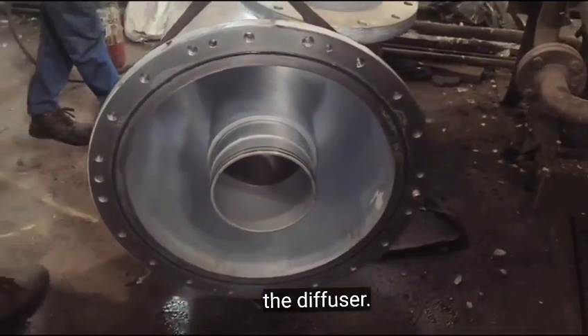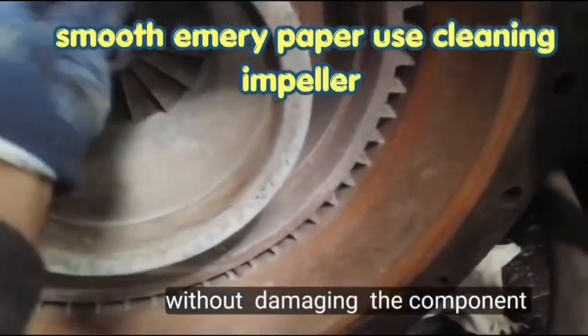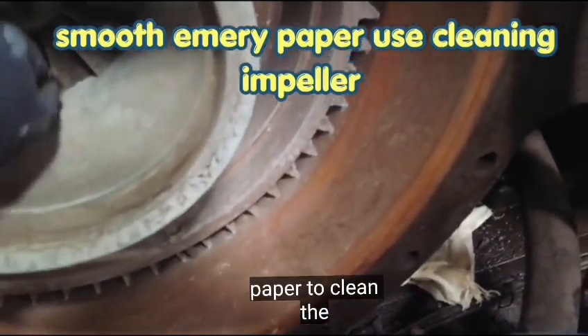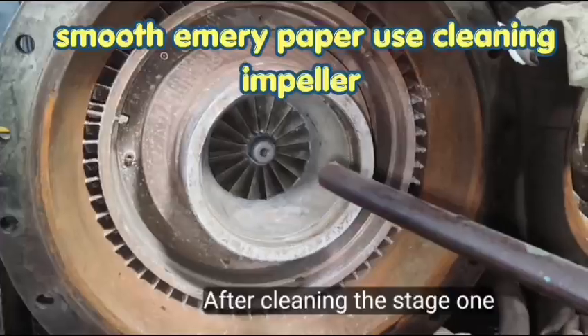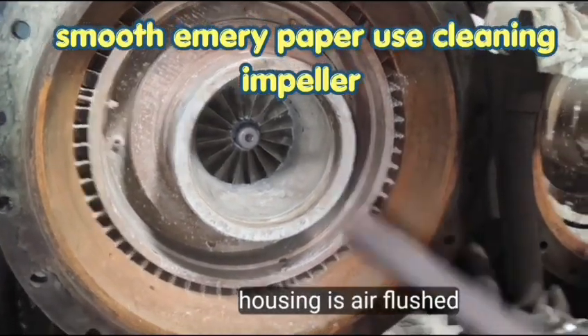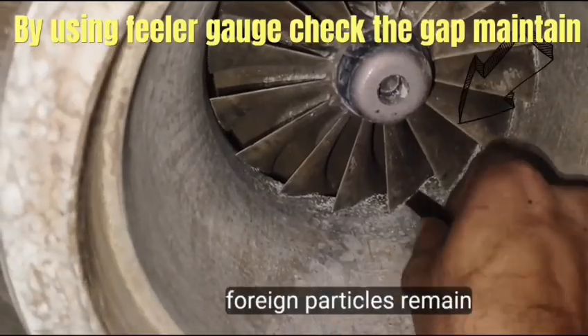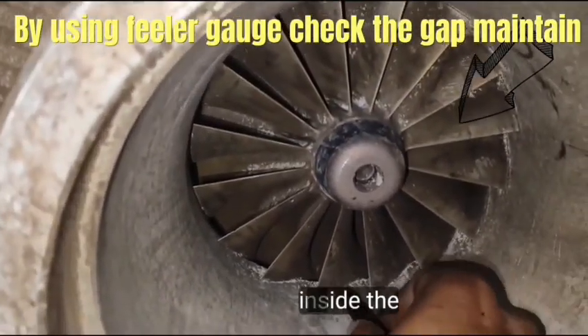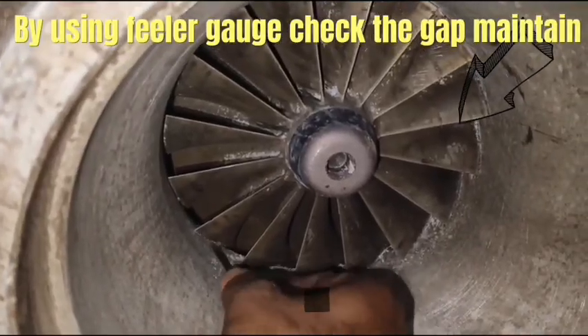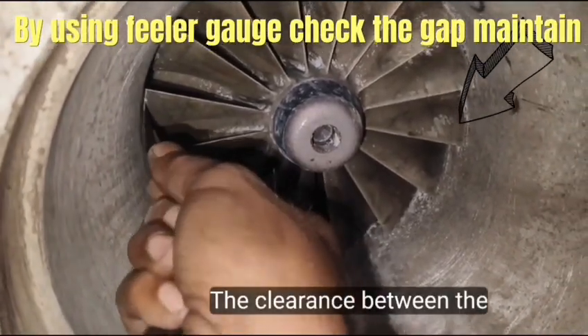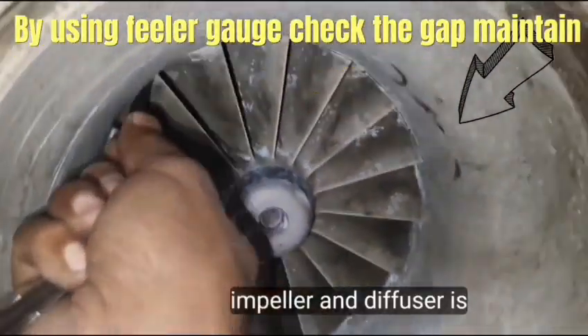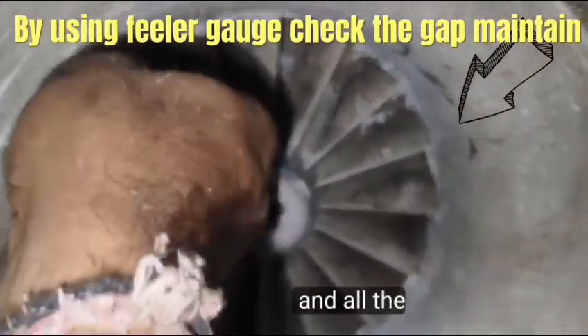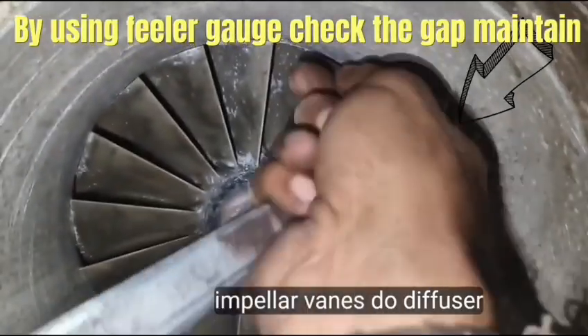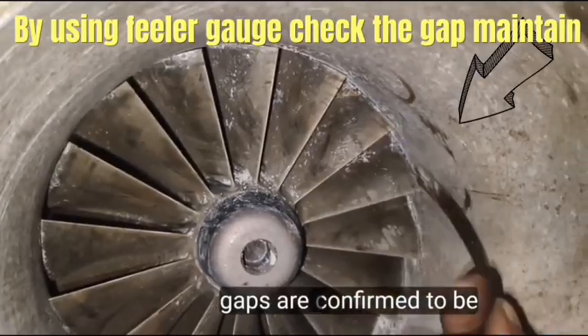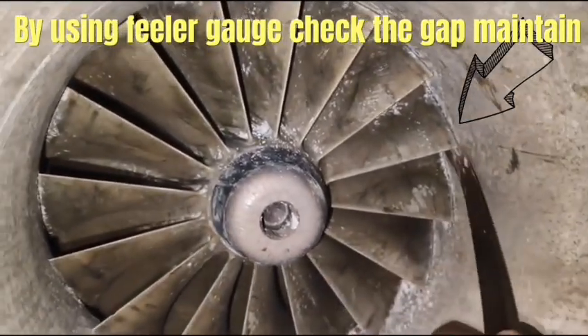Remove and clean the diffuser using a smooth emery paper to clean the diffuser and impeller properly. After taking the alignment, use a feeler gauge. Maintain the gap between the impeller and diffuser at 0.40 mm. All vanes gap is 0.40 mm. It is okay.